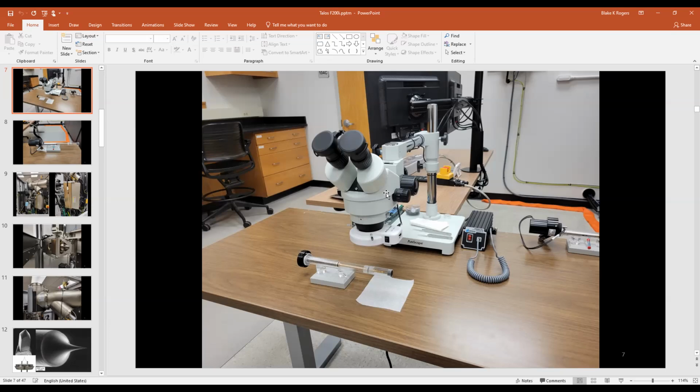Oh no, that's after we get done. So at the end of the day, we keep liquid nitrogen on that trap and it lasts for 6 to 10 hours. At the end of the day, I'm not coming back in the middle of the night to fill it up again. So I take it off of there, the cold finger starts to warm up. We start what's called the cryo cycle, and then it uses the turbomolecular pump instead of the ion getter pump all through the night until all of the water vapor and different things that have gathered on that cold finger have been removed from the column. And then the next day, you're ready to go, because it ends on its own.